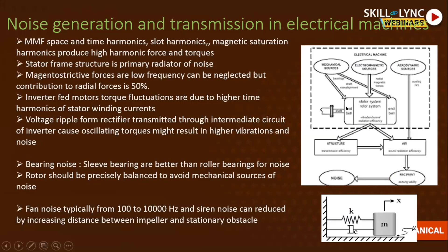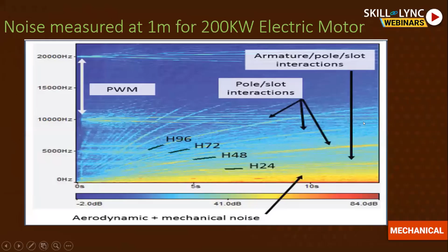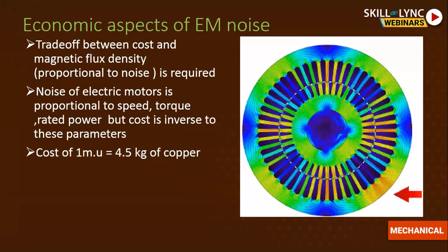You can reduce it by selecting good bearings. Also you can reduce it by having an inverter which has less torque fluctuations. You can also have the natural frequency of the stator frame or end bell separated from the magnetic field density radial forces frequency. So these are the different noise countermeasures that we can use to reduce the electric motor noise. So that is all I have with respect to electric motor noise.